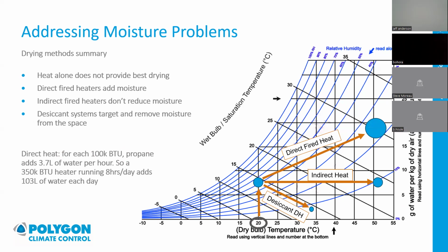So you've now increased your vapor pressure, which means that if your materials have less vapor pressure than that wet air you're making, the materials are going to take that moisture and they're going to suck it up, they're going to absorb it. So you are potentially creating a massive problem for yourself. Despite the lower RH, it's kind of an artificial lowering. Everything could actually get a lot wetter on your site.